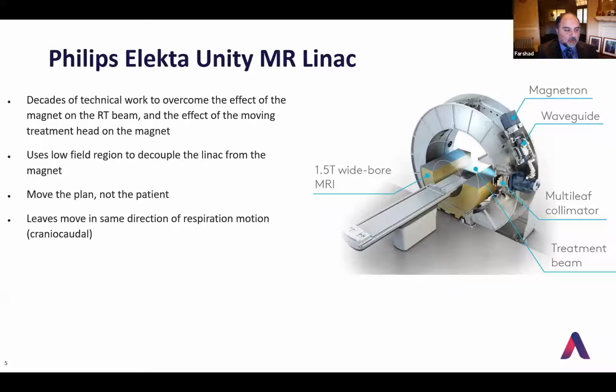This is what we purchased, a Philips Elekta Unity MR Linear Accelerator, which has been installed in our department. If you look at the cutaway, you can see there's an MR scanner in the middle of a donut, which is actually the gantry, a solid 3.6 meter circumference, which the linear accelerator rotates around. While this looks elegant, it has taken 2 decades of work to develop and commercialize, with most of the initial work occurring as an academic commercial collaboration led from Utrecht in the Netherlands.